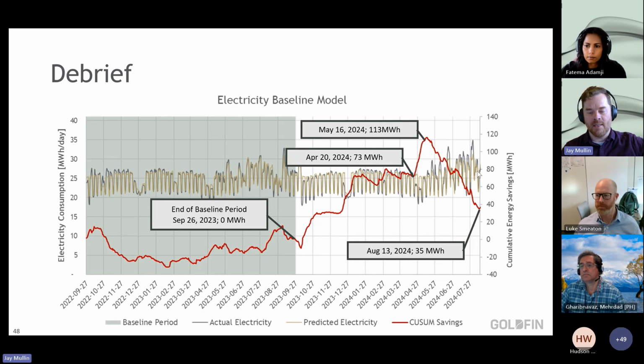So in that case you'd do a baseline adjustment, and there are different approaches to do that. We don't have time to get fully into it, but essentially what you'd do is quantify the energy impact of adding air conditioning to those buildings. Then you'd go back and adjust your baseline data, so your baseline period is now as if all those buildings had air conditioning during that period. That's what you modeled, and it flattens out this slope so it won't show up as that decrease.